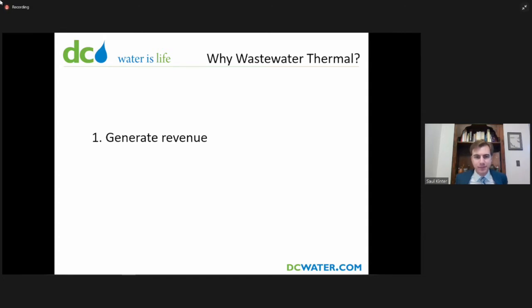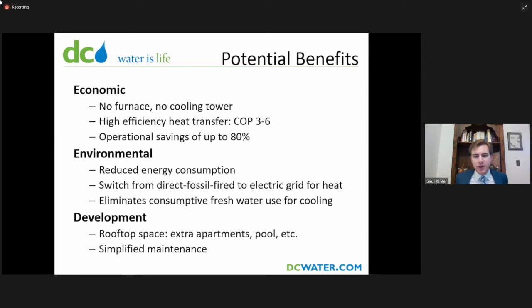If we go to the next slide. The idea here is that the water in our sewers is a potential source of heating and cooling energy. We are able to take advantage of the relatively neutral temperatures of wastewater throughout the year to more efficiently heat and cool than we can using fossil fuels in a furnace, or just electricity in an air conditioner or an electric resistance heater or something like that. The use of the neutral temperature reservoir increases the efficiency, allows for savings in terms of both dollars and energy, and enables, in DC, a particular extra value: the ability to move equipment off the roof.